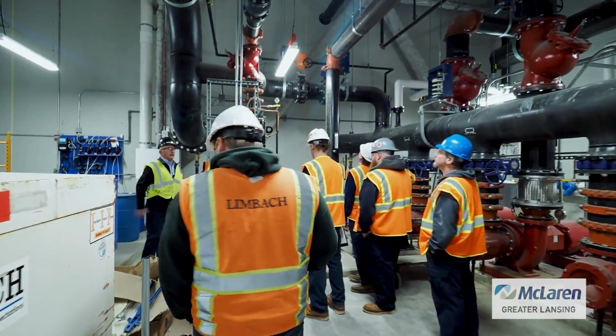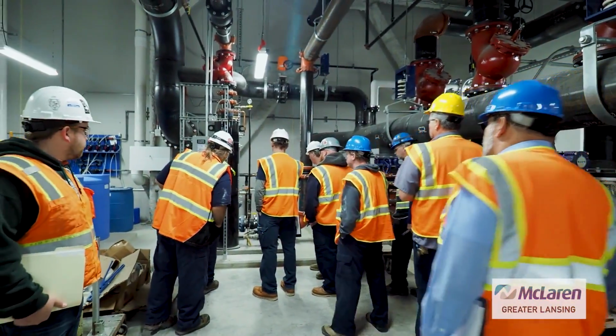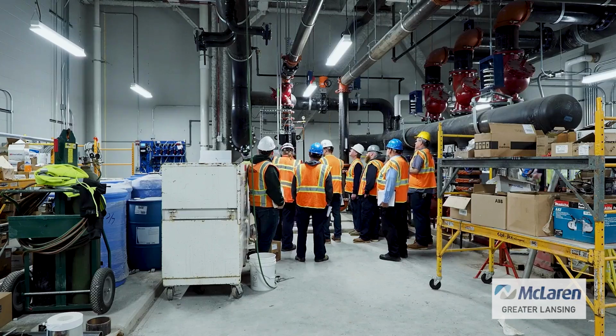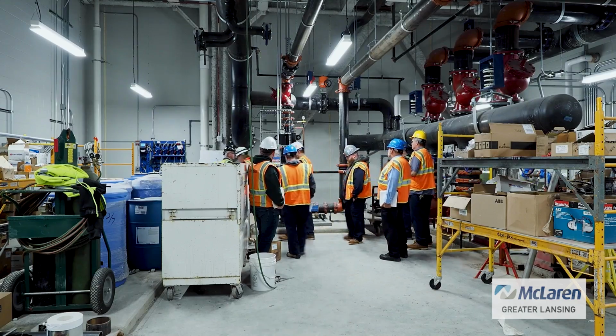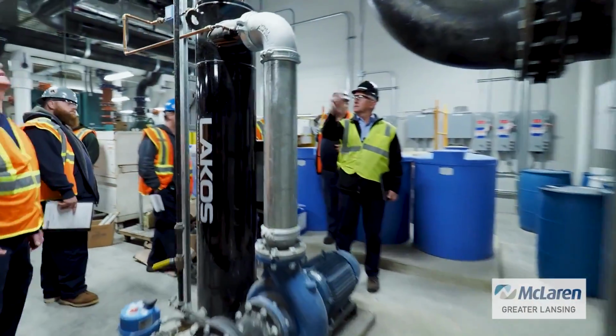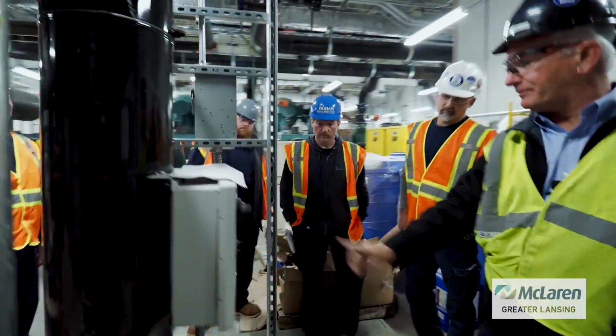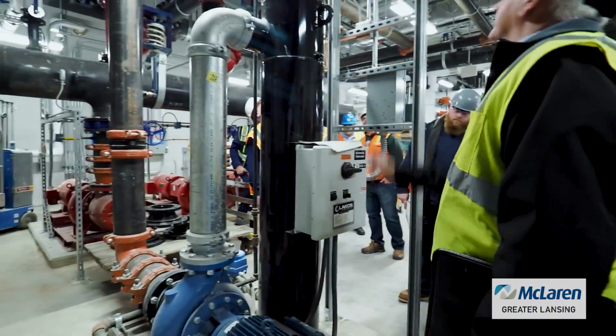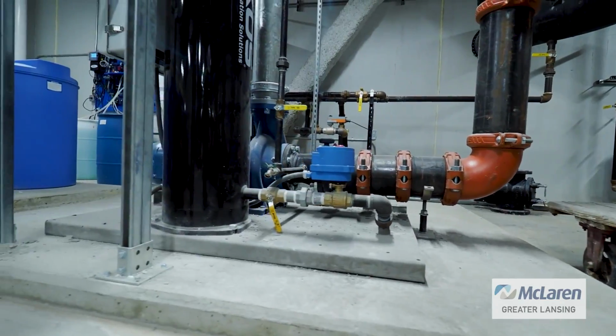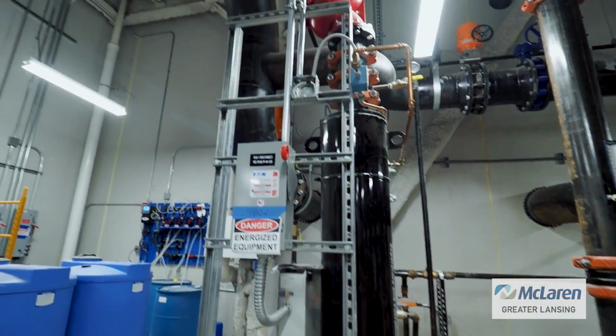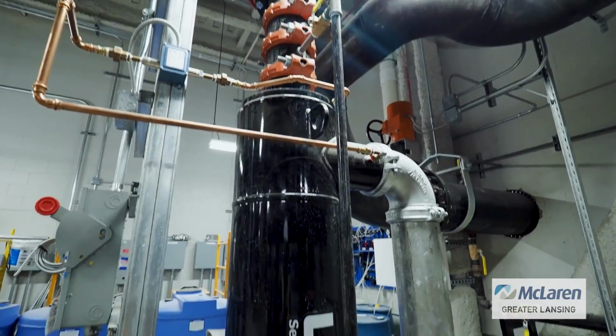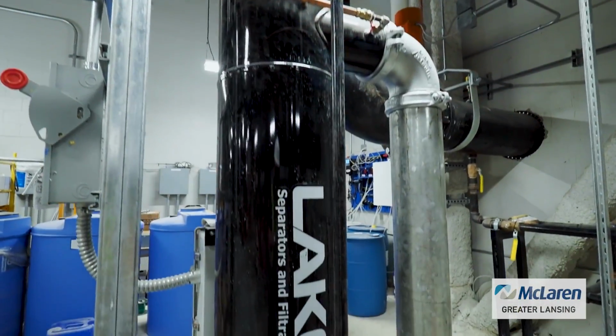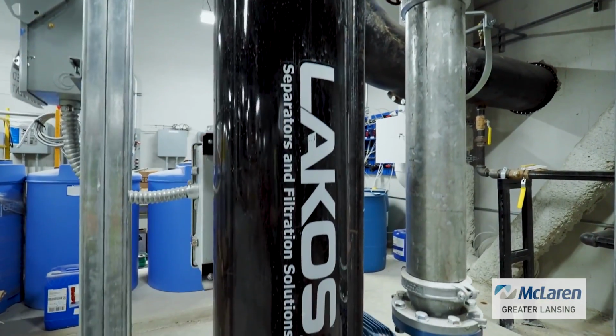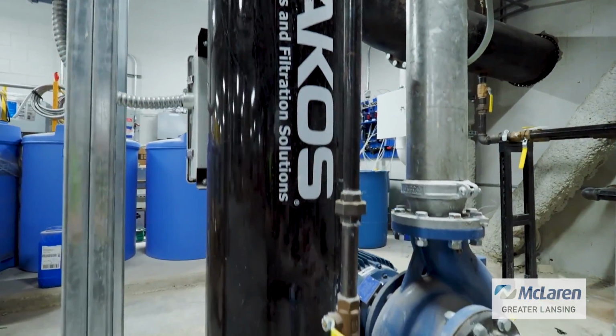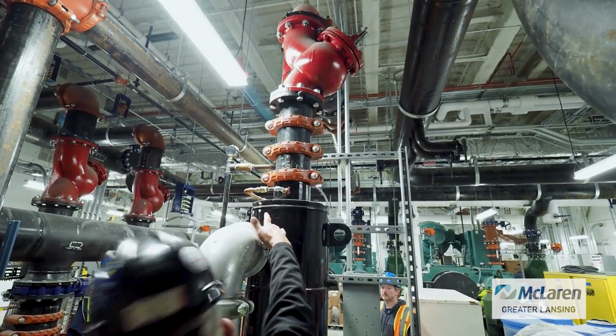Here's your separator, your filter. I don't know why it's not running right now, but it's not. It draws water off the system, side streams it, does the centrifugal separation, solids collect in the bottom, clean water goes back up and out. Purges to that drain right there. Anytime a condenser pump's on, I'd run this. Right now, the disconnect switch is off, and the hand-off-auto switch is off. So normally we have a gauge here.